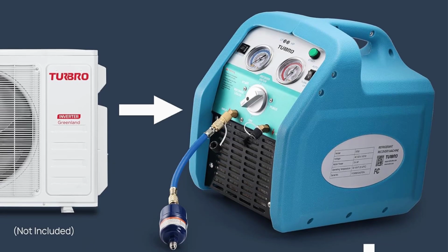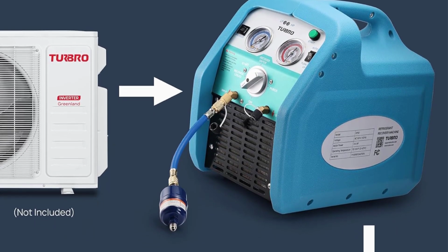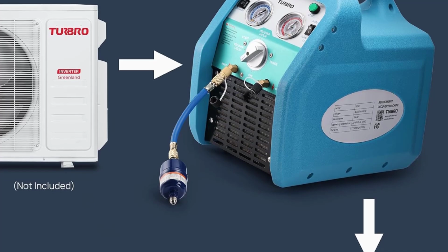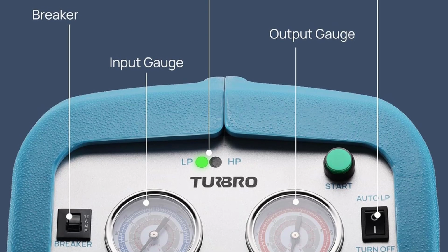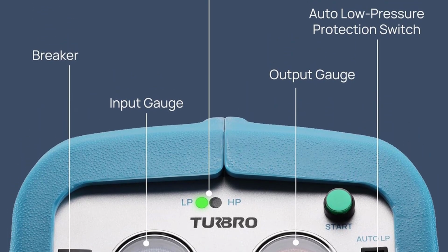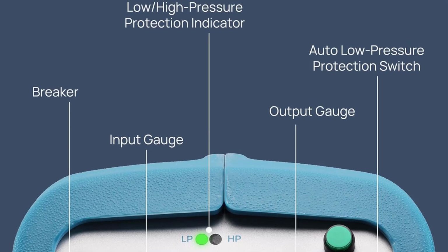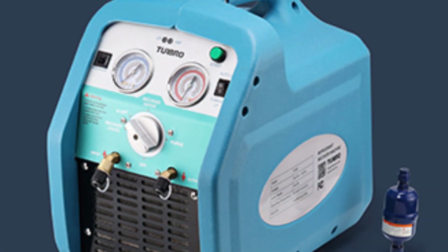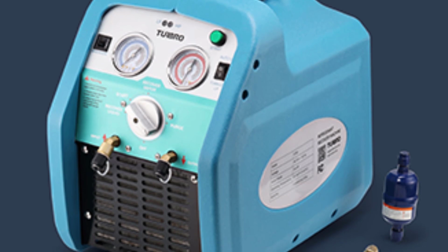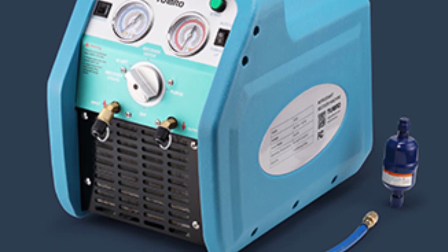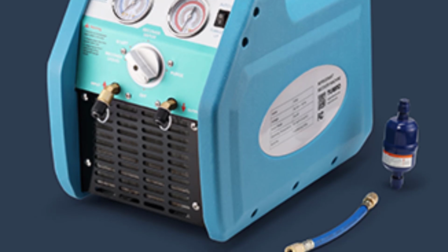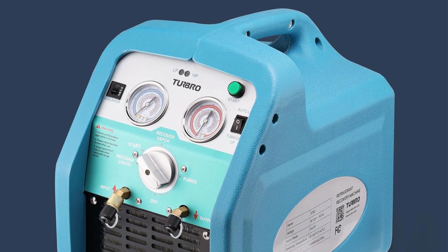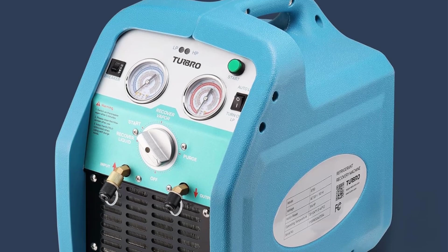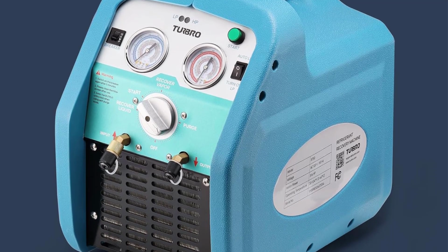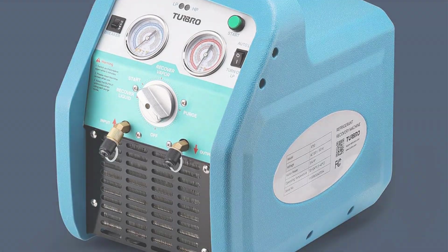One of the standout features is the dual pressure gauges, giving you real-time data so you always know what's happening inside the system. It automatically shuts down when pressures get too high or low, which means you're protected every step of the way. The single knob operation makes switching modes surprisingly simple, even when you're dealing with larger systems holding over 22 pounds of refrigerant. With compatibility across a wide range of refrigerants like R410A, R1234YF, and R454B, plus a built-in filter dryer to keep things clean, this machine is built to make your work easier, safer, and more efficient.